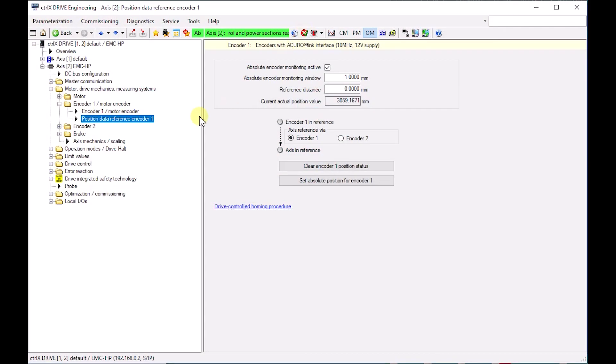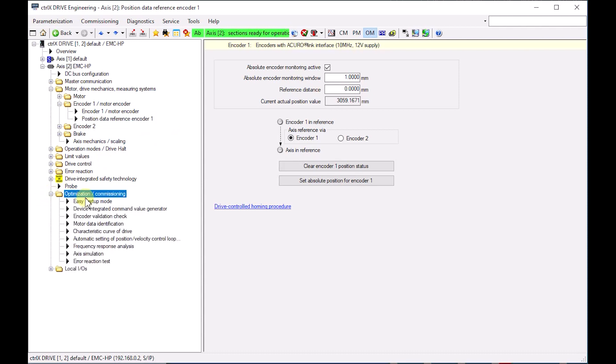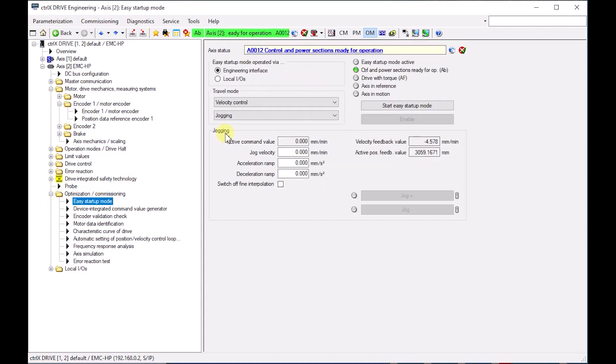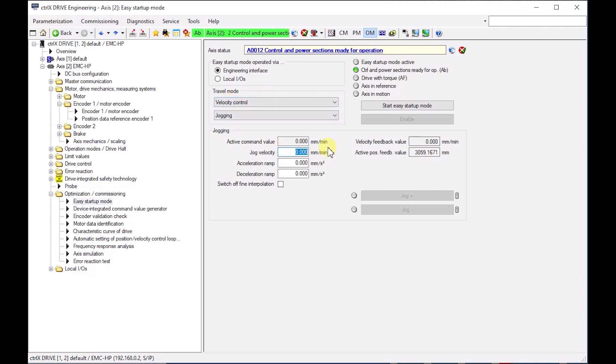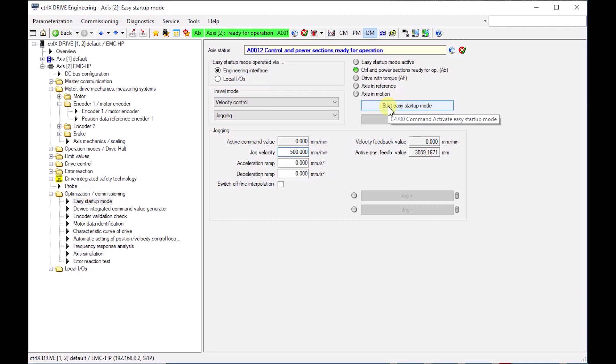If the physical position of the actuator is not set to the zero measure LREF, use the easy startup mode to move the piston rod. Use jogging as travel mode, enter a jogging velocity, start the easy startup mode, and power up the drive.